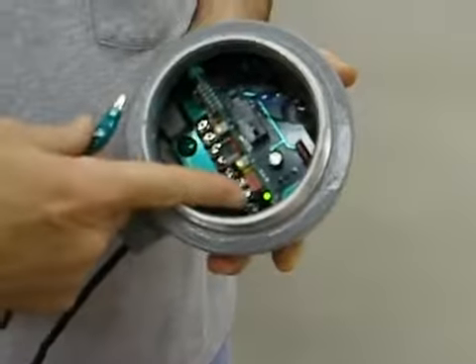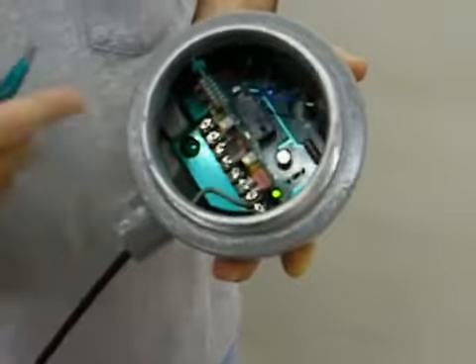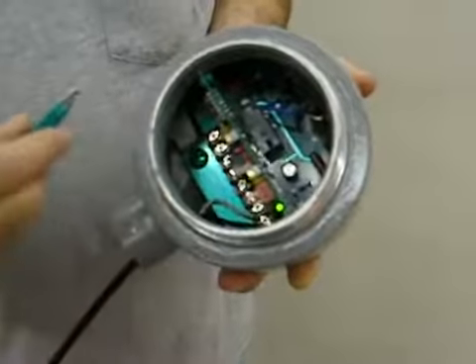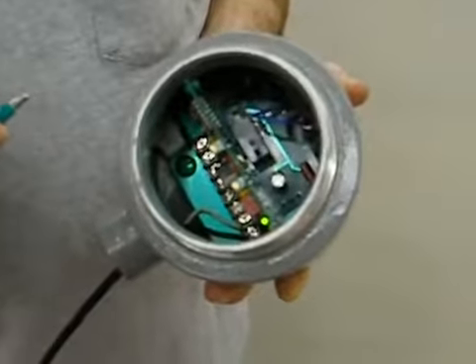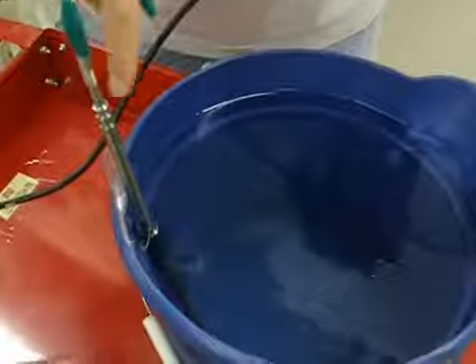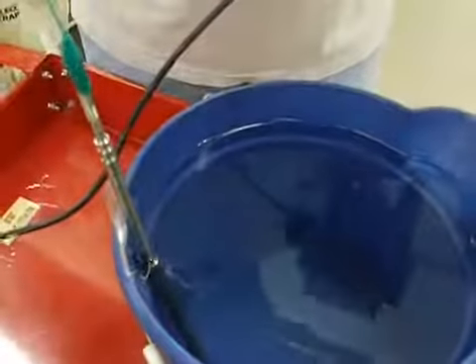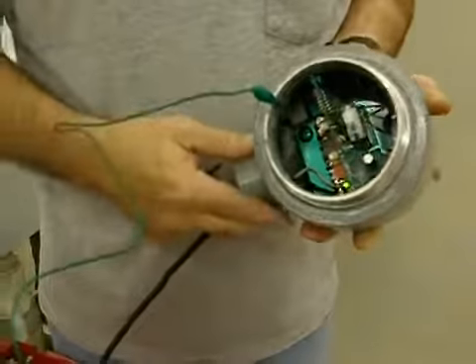The green LED is on because it's in the automatic fill mode, and now that both LEDs are off, it realizes the water is below the probe, so the relay is energized to call for the solenoid to be open and deliver more water. In my bucket, I have a steel rod to ground the water and a little jumper here that I'll just put here for the sake of demonstration. Now we're going to calibrate it.